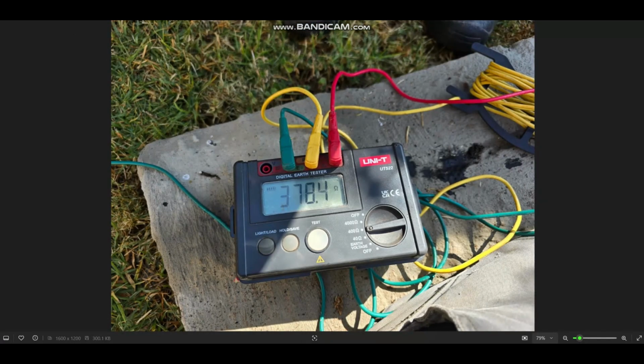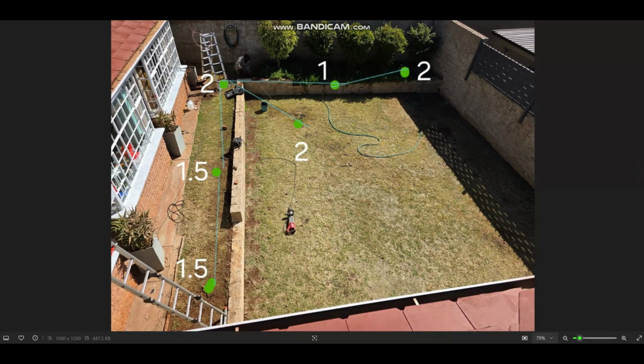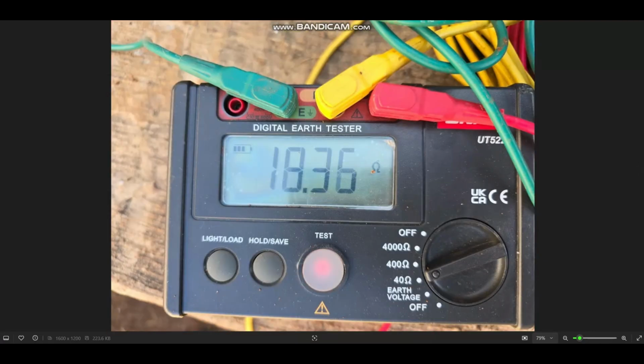Here you can see we put in one earthing spike for a house high up on bedrock, and the first earthing spike exhibited 378.4 ohms. And what that would do if it got hit by lightning, it's just going to send that voltage straight back to your inverter system. So we had to add a few more spikes. Here's a 1.5 meter, here's a 1.5 meter, here's a 2 meter, etc., etc. So 6 earthing spikes later, we got the resistance down to under 20, and the client was happy. Best practice would demand under 10, but the client was happy with this scenario.